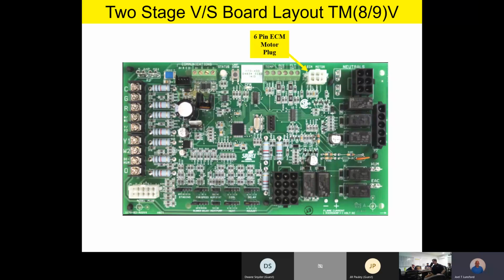The variable speed control board is a totally different control scheme. So here we're going to have a 6-pin plug that's going to go down and tell the motor what to do. And all of our airflow jumpers are going to be jumpered on this board right here. So we're not going to be going down to the motor and making speed tap changes with this type of control scheme. We're going to just tell the motor what to do by way of this 6-pin plug. And any airflow jumpers, airflow measurements, or airflow adjustments we want to make, we're going to make down at the bottom of the board with airflow jumpers, which we'll discuss here shortly.